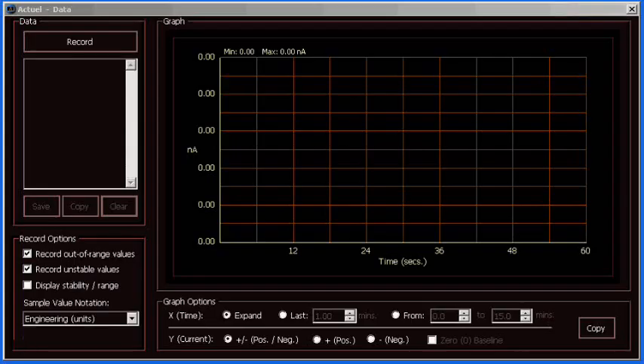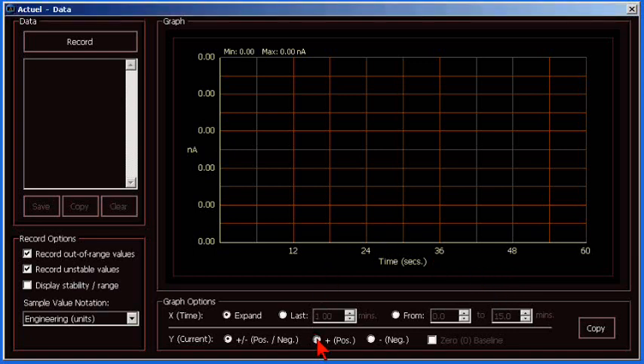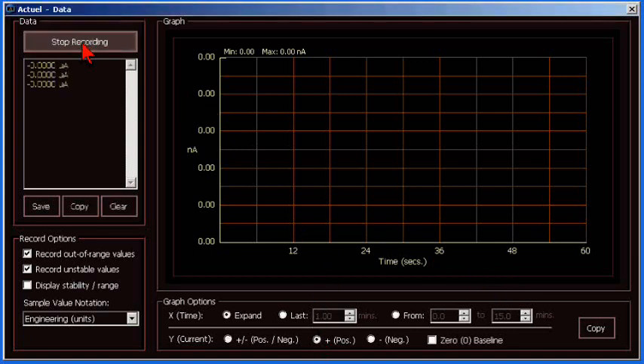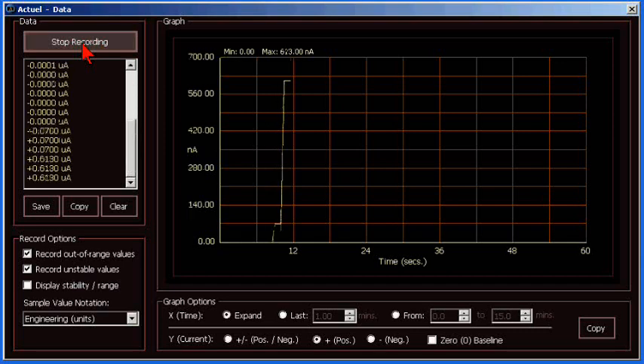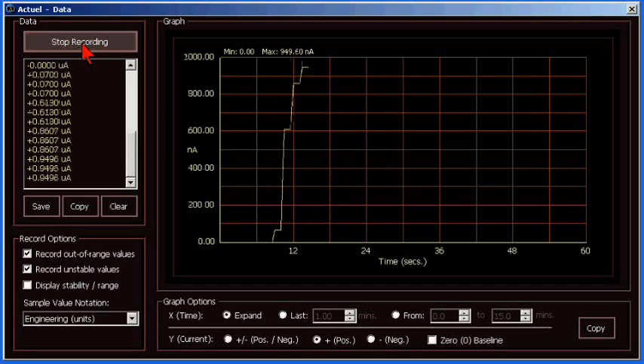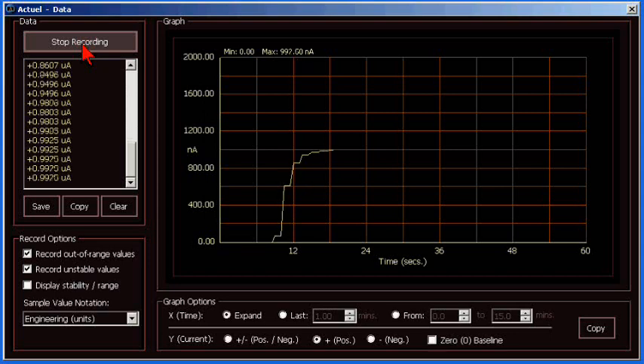Okay, let's look at the positive graph type. I have to select positive. And then start recording. When I put positive one microamp into the 9103, the graph goes positive to one microamp.